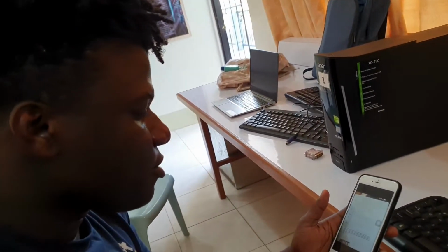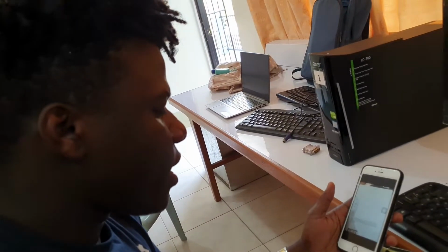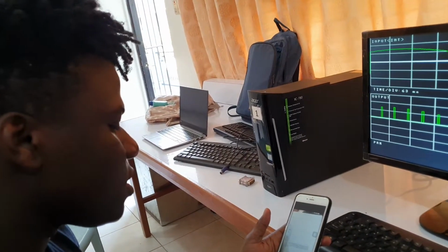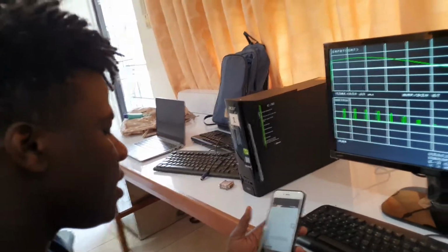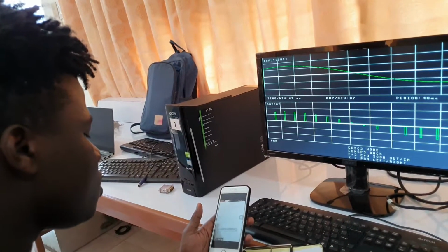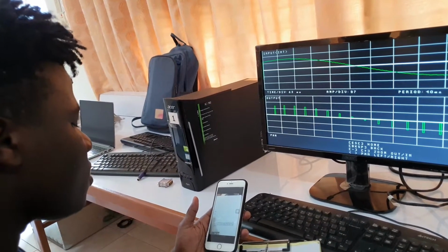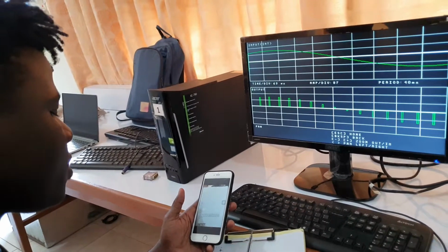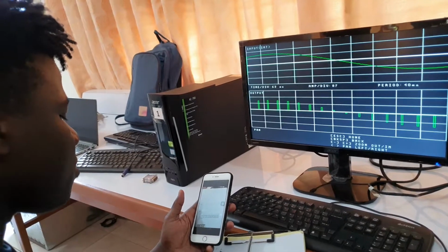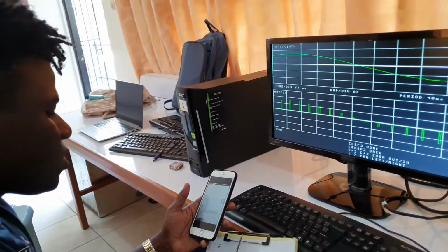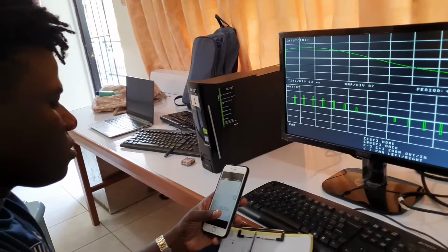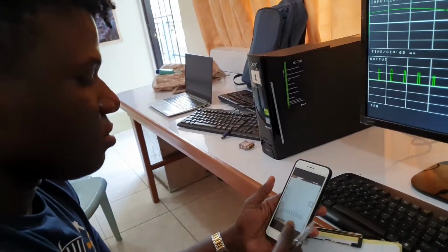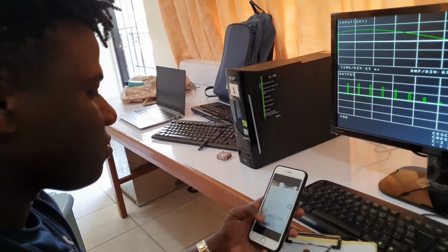Case 1 has the default settings. Case 2A and case 2B have constant input frequency while changing the sampling frequency. Case 3A and 3B have changing input frequency while having a constant sampling frequency. Based on the observations, relate the input frequency and the pump sampling frequency to the pump output. You have to compare the cases to each other and put an answer.